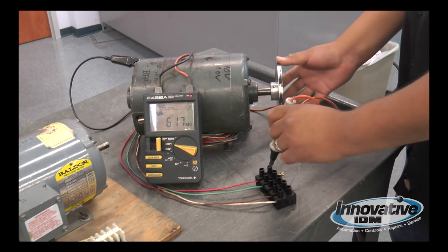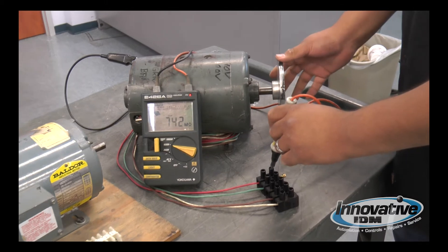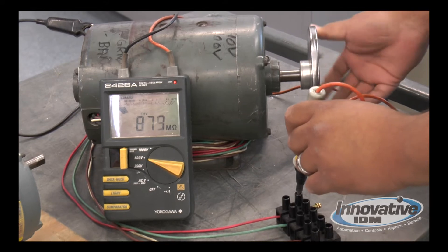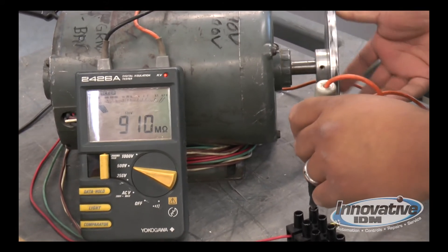What we're checking for is the motor not to be short with the chassis. We'll spin the motor. It'll read in the high megs, eight to nine hundred megs.